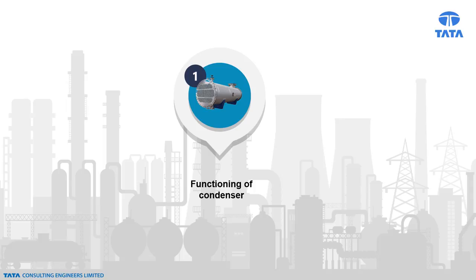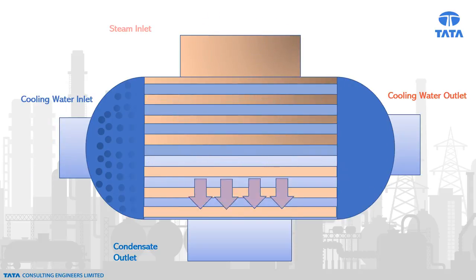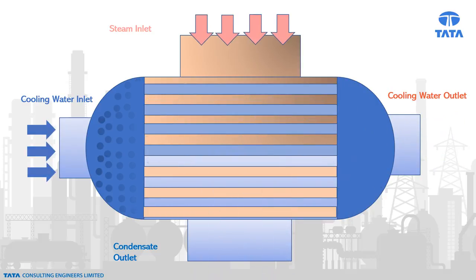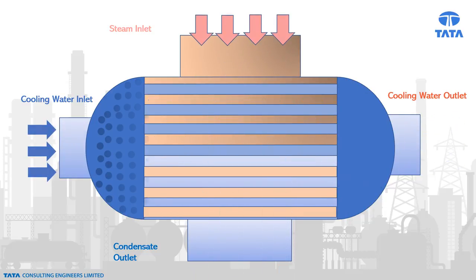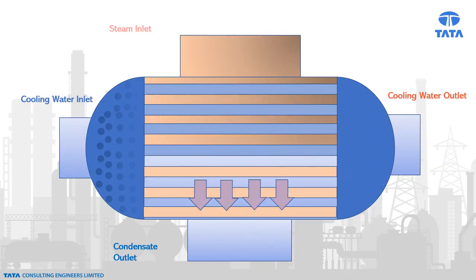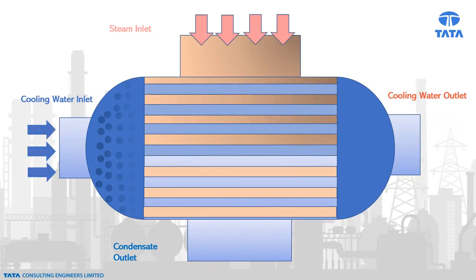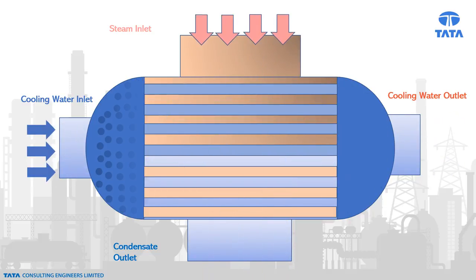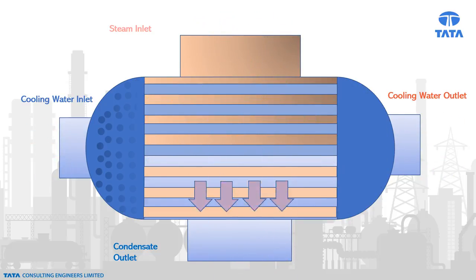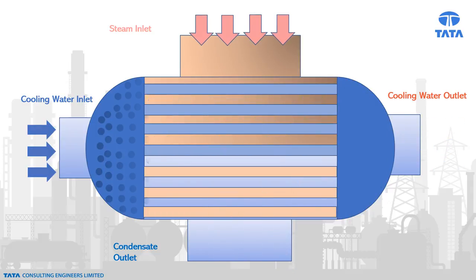Let's look at the functioning of the condenser. Steam condensers are an inevitable equipment in power plants. The purpose of a surface condenser is to condense the exhaust steam from a steam turbine to obtain maximum efficiency, and also to convert the turbine exhaust steam into condensate so that it can be recirculated through the boiler as feed water. The condenser is designed as per the Heat Exchanger Institute, or HEI, to operate at a defined vacuum level, considering various parameters such as steam flow, cooling water flow, heat transfer area, terminal temperature difference or TTD, etc.